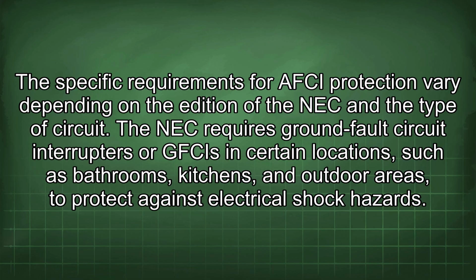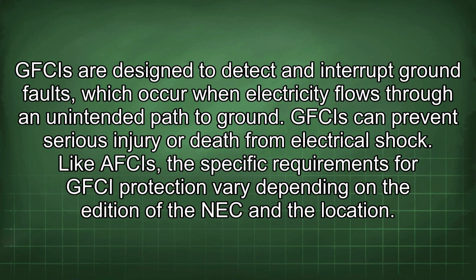The NEC requires ground fault circuit interrupters, or GFCIs, in certain locations such as bathrooms, kitchens, and outdoor areas to protect against electrical shock hazards. GFCIs are designed to detect and interrupt ground faults, which occur when electricity flows through an unintended path to ground. GFCIs can prevent serious injury or death from electrical shock. Like AFCIs, the specific requirements for GFCI protection vary depending on the edition of the NEC and the location.